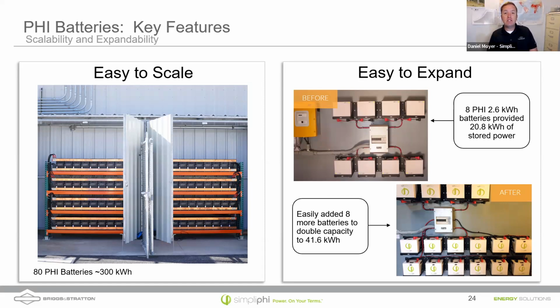The picture on the left is an airport hangar in Hawaii, where we've scaled up 80 of our batteries to get to 300 kilowatt hours. I really like that picture because of all those cool copper bus bars you see. We always want to wire our batteries in parallel, never series, and that's what you're seeing there.